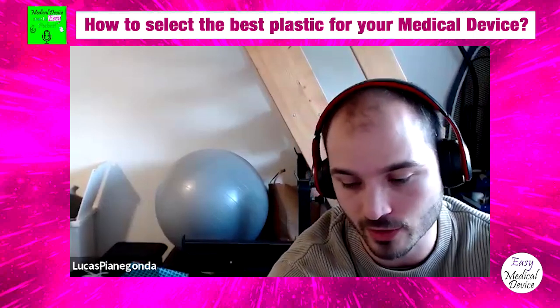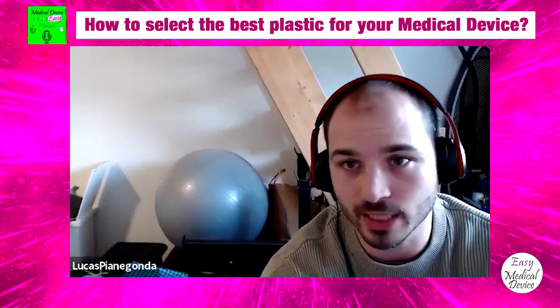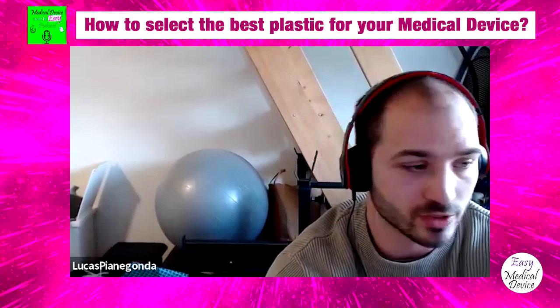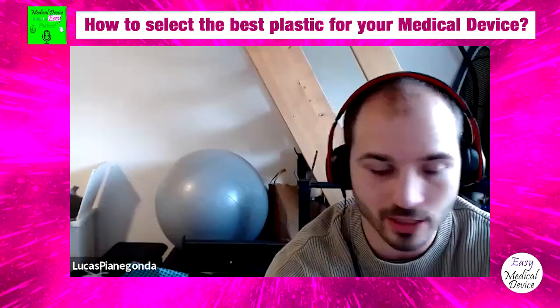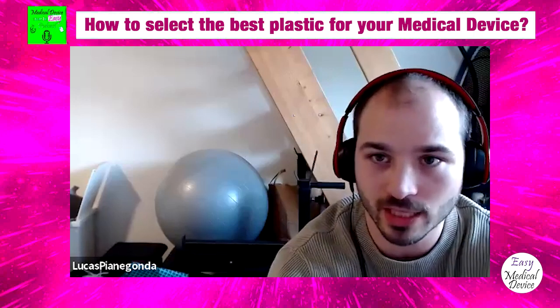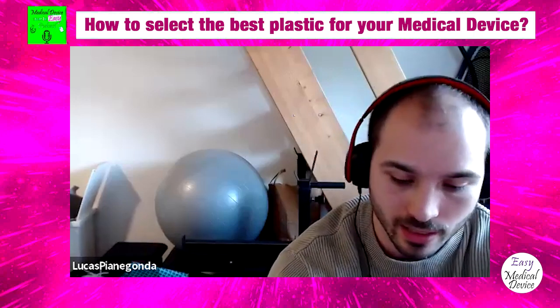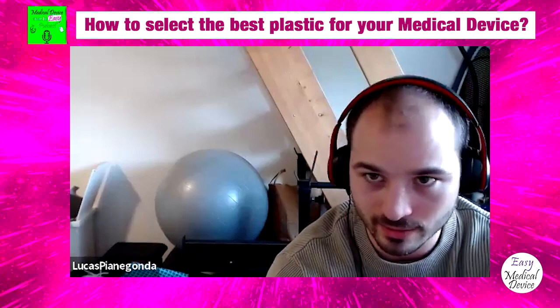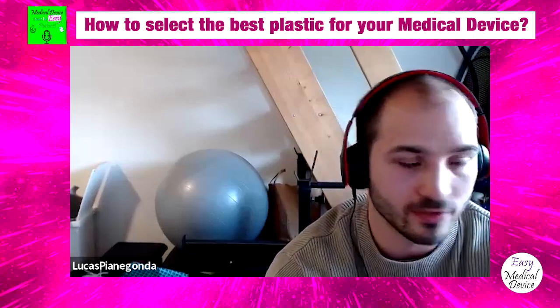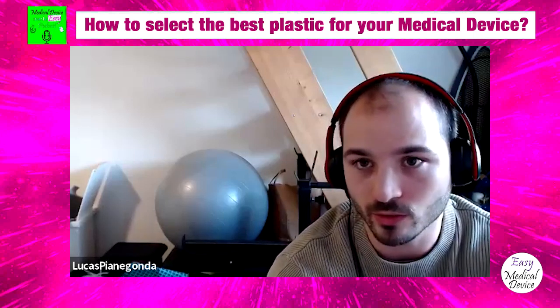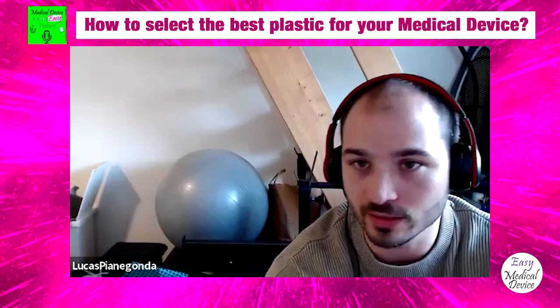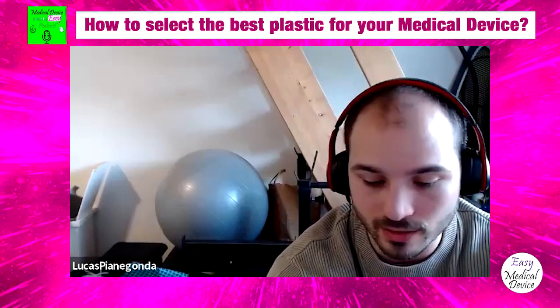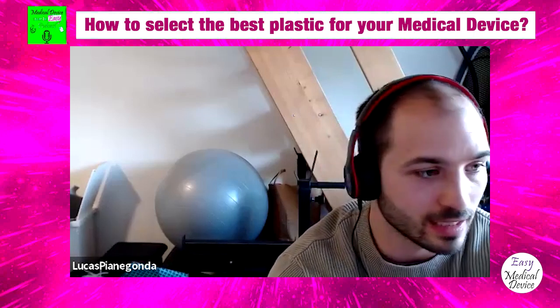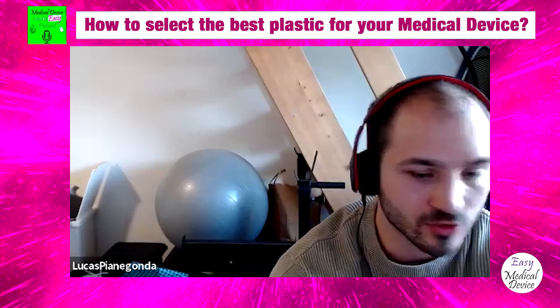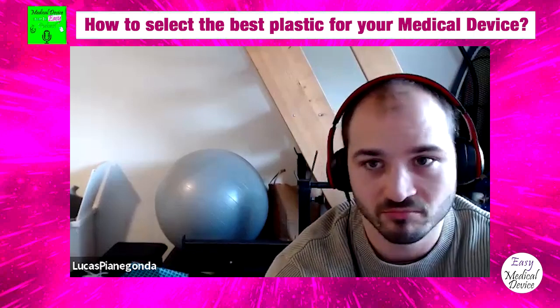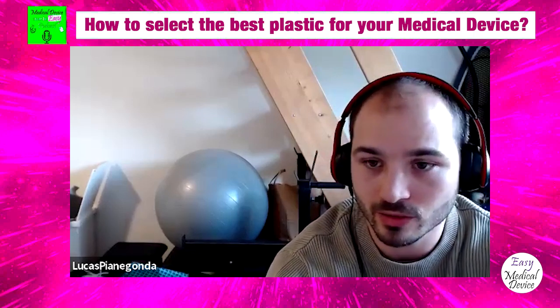So the plastic manufacturers. And if you make an implant from that, that's very critical. There's an unacceptable risk there. If there would be a change in formulation, you couldn't guarantee that this device is safe and effective. If you have a very low risk device, crutches or things that are not in direct patient contact, like an electronics cover or something like that, you don't need to know every change.